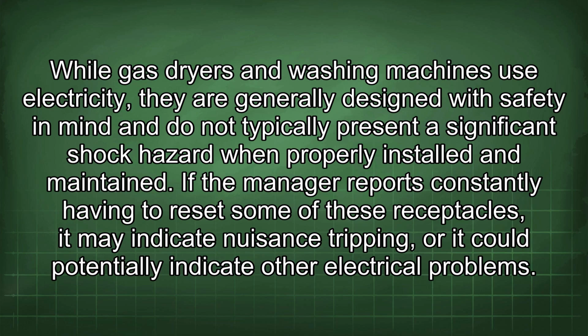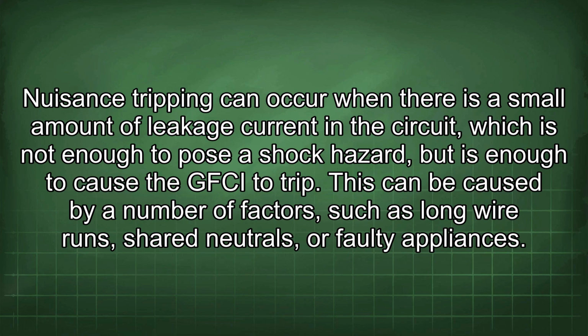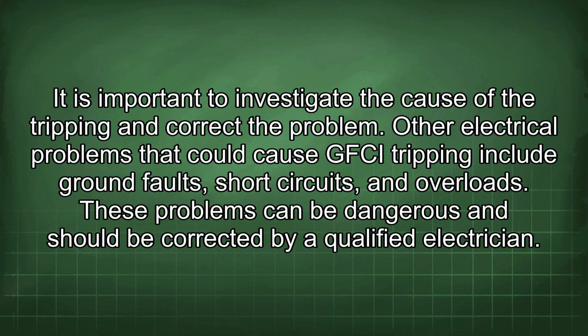If the manager reports constantly having to reset some of these receptacles, it may indicate nuisance tripping, or it could potentially indicate other electrical problems. Nuisance tripping can occur when there is a small amount of leakage current in the circuit, which is not enough to pose a shock hazard, but is enough to cause the GFCI to trip. This can be caused by a number of factors such as long wire runs, shared neutrals, or faulty appliances. It is important to investigate the cause of the tripping and correct the problem.